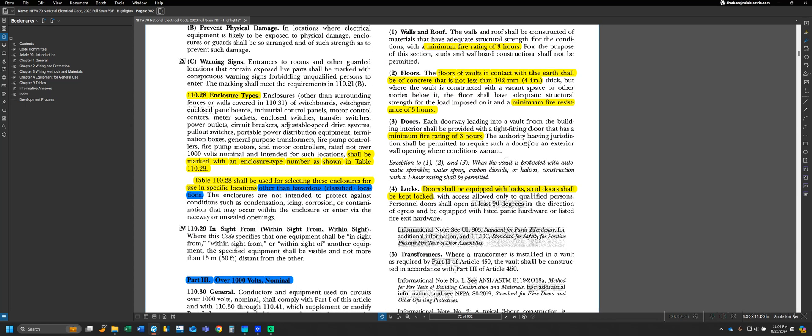As a general note for vaults, we can see that any doors on those vaults have to be equipped with a lock, and they have to be kept locked with access only to be provided to qualified persons. These are just some general requirements for vaults that we see that tie back to our enclosure types.